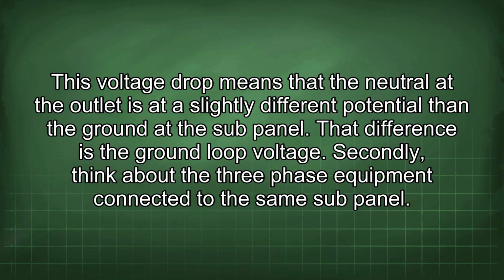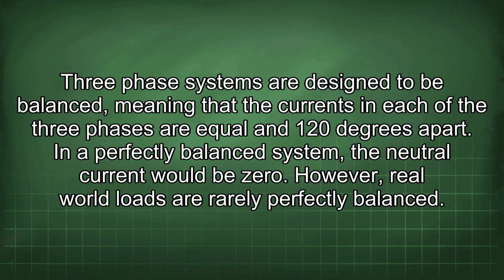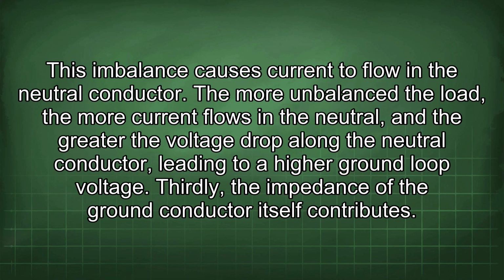Secondly, think about the three-phase equipment connected to the same sub-panel. Three-phase systems are designed to be balanced, meaning that the currents in each of the three phases are equal and 120 degrees apart. In a perfectly balanced system, the neutral current would be zero. However, real-world loads are rarely perfectly balanced. This imbalance causes current to flow in the neutral conductor. The more unbalanced the load, the more current flows in the neutral, and the greater the voltage drop along the neutral conductor, leading to a higher ground loop voltage.